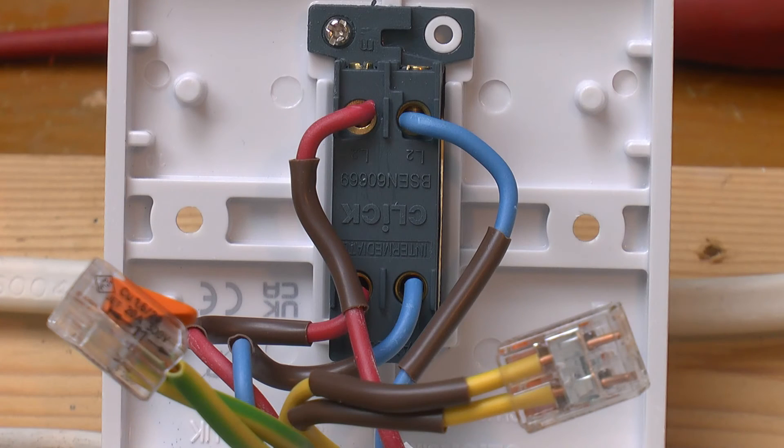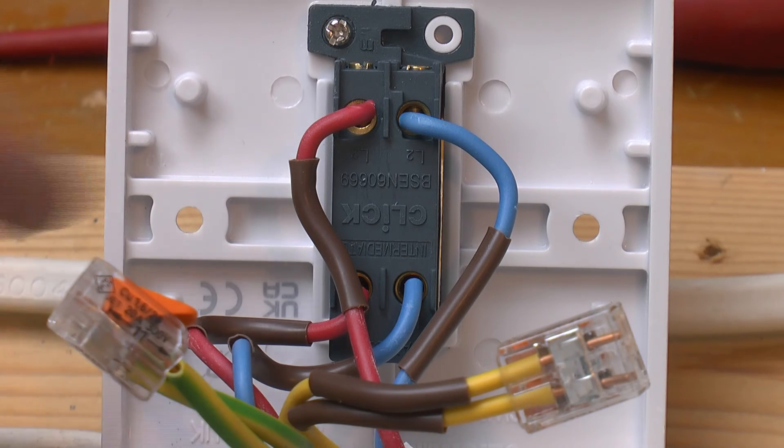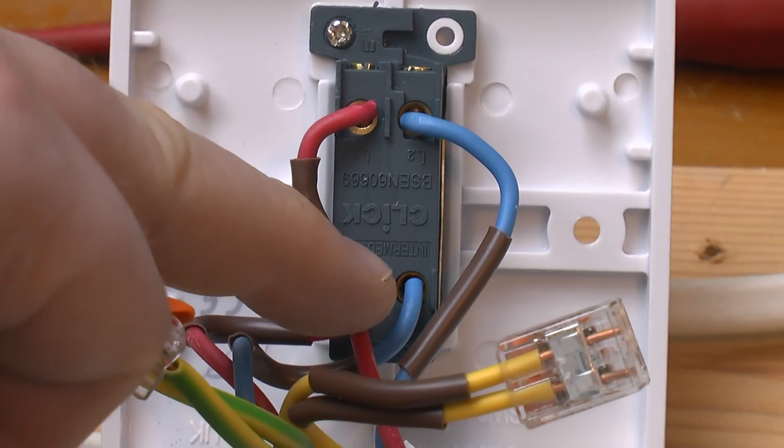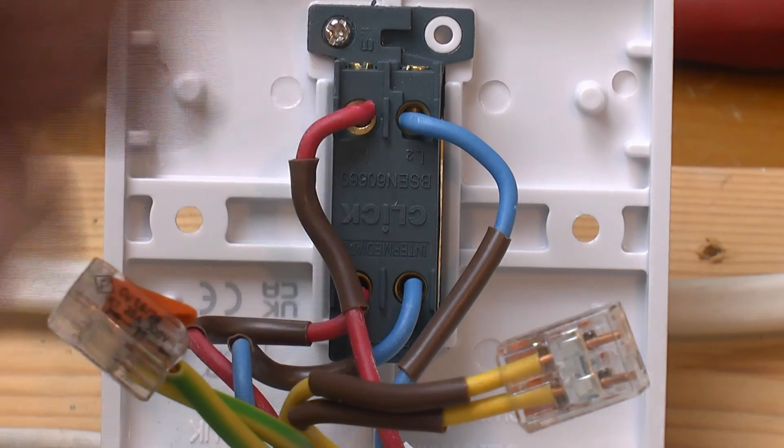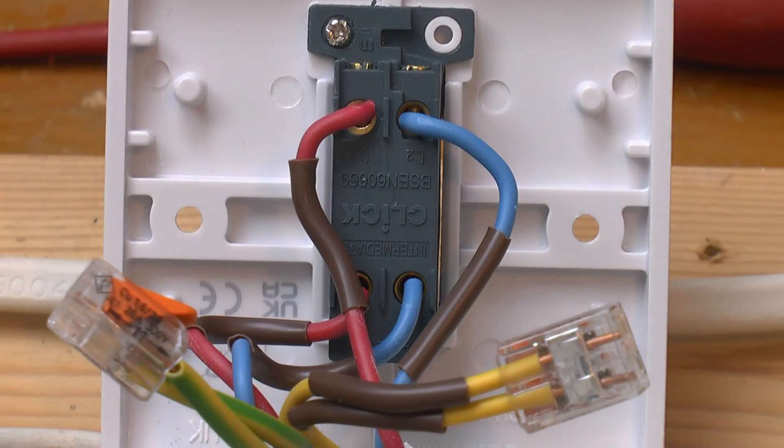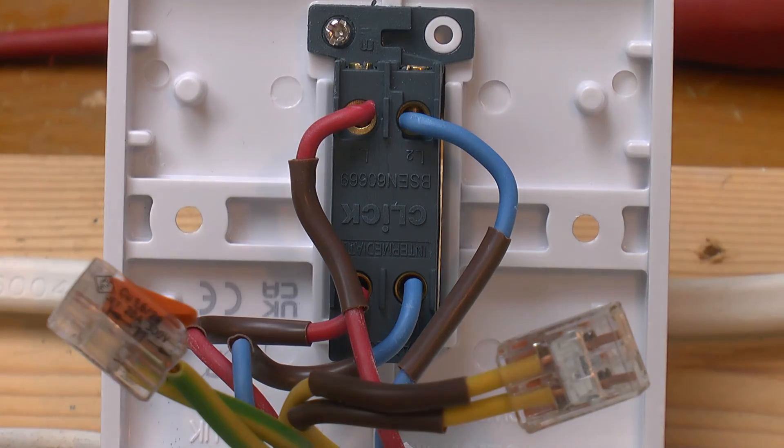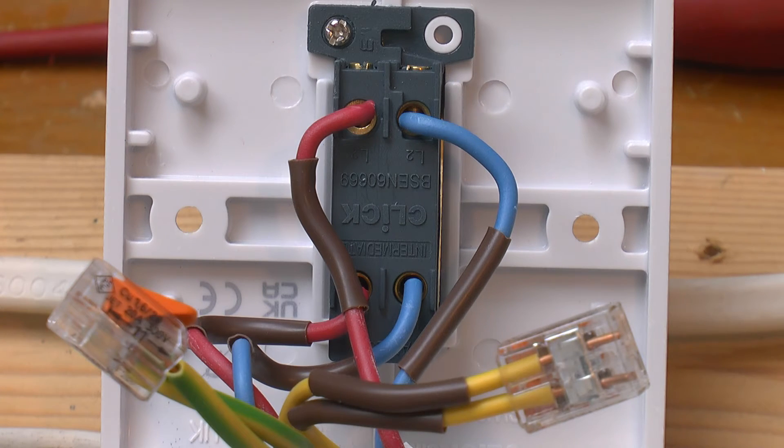What's interesting here, and is the reason I didn't label the terminals on the diagram, is the intermediate switch. This has two connections marked L1 and two marked L2. So the L1 to L1 conductor goes through the L1 terminals and the L2 goes through the L2 terminals, right? Wrong.